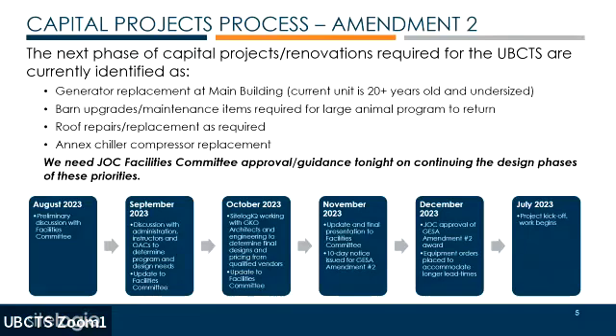As far as the generator is concerned, is it possible to supplement it with an additional smaller generator instead of replacing it? Anything is possible, but the problem is you'd have to put in two brand new smaller switch gears, run a secondary feed, end up doing a lot of the same work without solving the other problems, and you don't really have the pad space since you still need access.